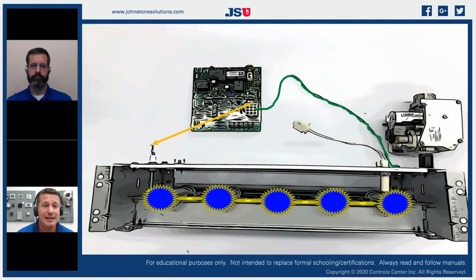That orange wire has high voltage on it. It's not a sensor. It has applied high voltage, typically between 50 and 80 volts AC, depending on the manufacturer of the control. You can take your meter and walk right over to it, and you can go straight from ground to the tip of your flame rod, and you have AC voltage.